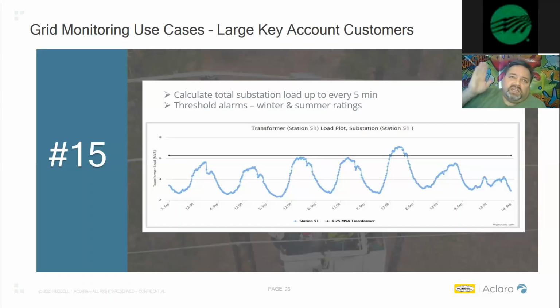What we can do is take all of those line monitors you have. Say this particular sub has 7 feeders coming out of it, and you put a sensor per phase - ABC phase, 3 per feeder, 7 feeders, 21 sensors. We can make a virtual aggregate of that transformer and monitor it, alert and alarm, and send you emails and texts off of that. So everybody's going along happy until you hit this section - a threshold you'd like to know every time your transformer goes above that particular number. We give that sub a little extra love, monitoring it just a little extra.